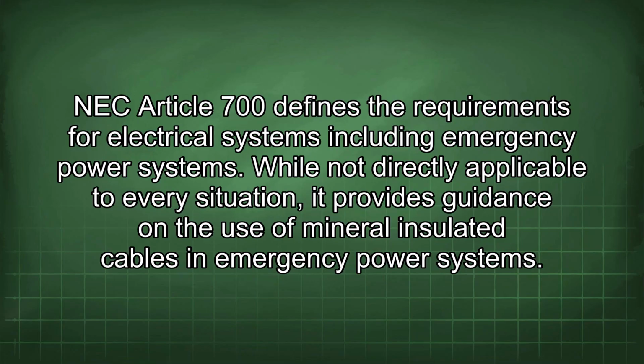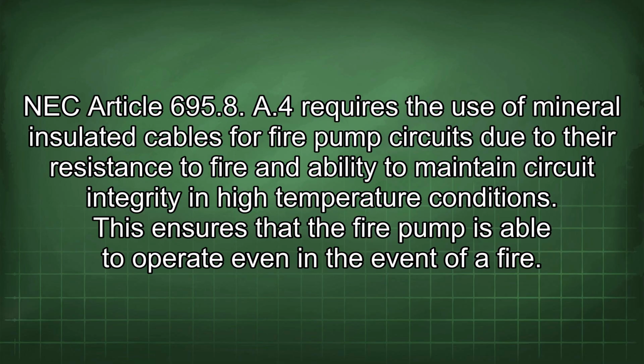NEC Article 700 defines the requirements for electrical systems, including emergency power systems. While not directly applicable to every situation, it provides guidance on the use of mineral-insulated cables in emergency power systems. NEC Article 695.8 A4 requires the use of mineral-insulated cables for fire pump circuits due to their resistance to fire and ability to maintain circuit integrity in high-temperature conditions. This ensures that the fire pump is able to operate even in the event of a fire.